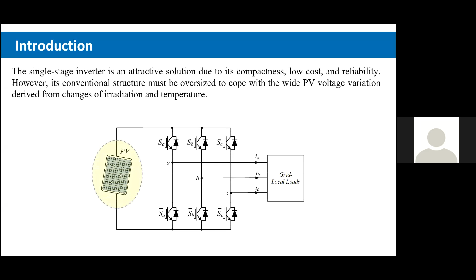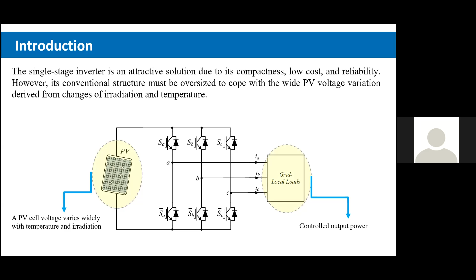As you can see in this slide, typical single-stage PV inverters. Photovoltaic cell voltage varies widely with temperature and irradiation, but the traditional voltage source inverter cannot deal with this wide range without overrating the inverter. The input DC voltage must be greater than the peak AC output voltage because the voltage source inverter operates as a buck converter, and we also need controlled output. Since we have a limited voltage range, it is better to introduce some solutions to solve this issue.